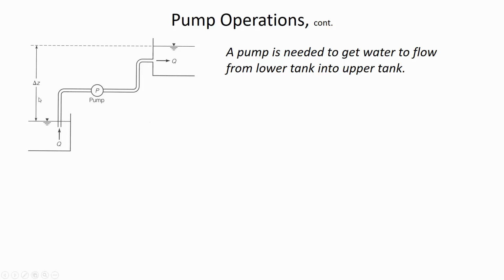Now, how much flow rate? It all depends on how big the delta Z is, what the losses through the pipe are. There are a lot of factors that can affect the flow rate, and we can put all of those factors into a rearranged version of the energy equation. And we can even graphically summarize what we call a system curve. Now, a system curve is a graph of how much head is required to achieve a certain flow rate.